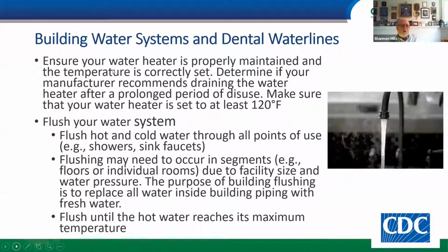Now, you want to make sure when you do this, your water heater is properly maintained, because water heaters and hot water sometimes tend to increase the amount of Legionella present. You have to flush your system. I mean, not just your water lines. We'll get to that in a second. You need to flush all of the water lines, all the faucets, shower heads, even the toilets and urinals in your office. And flush both hot and cold water to all points of use.